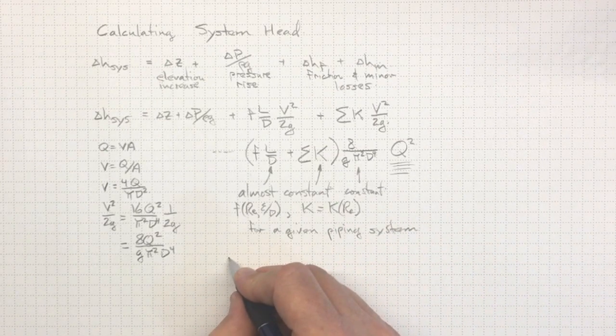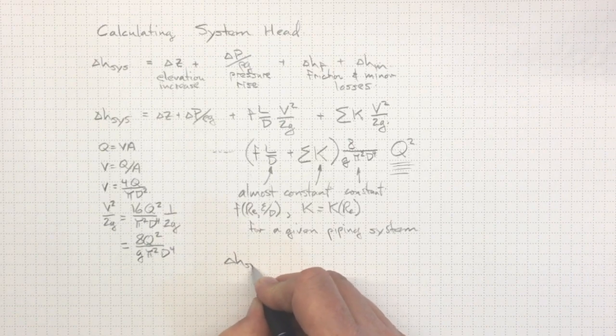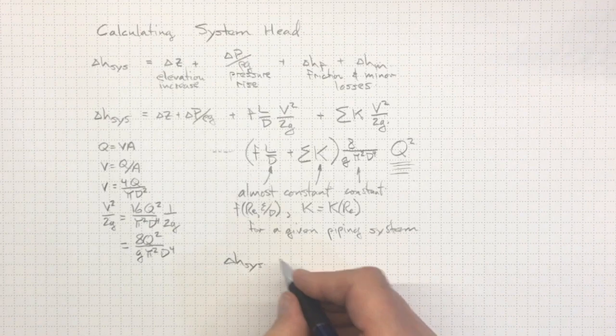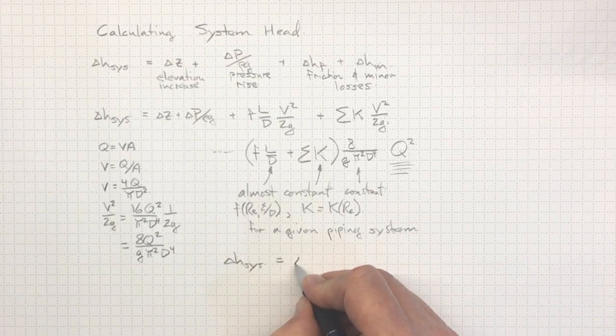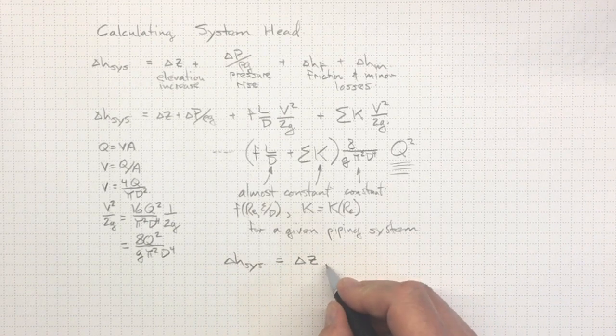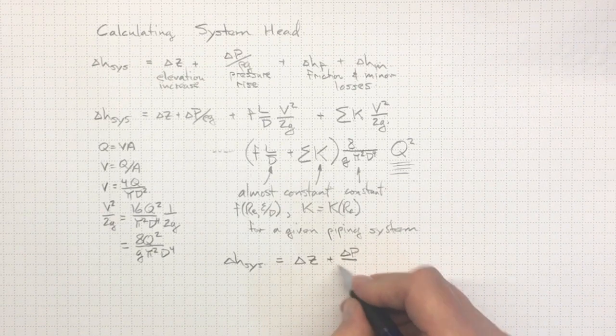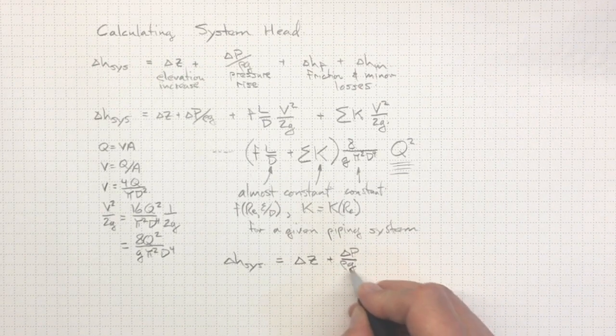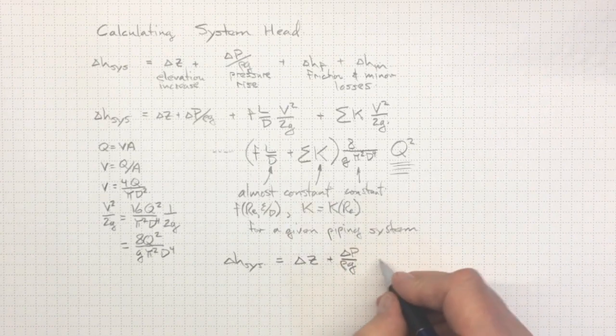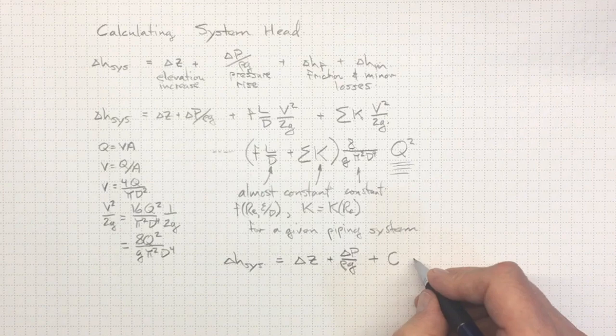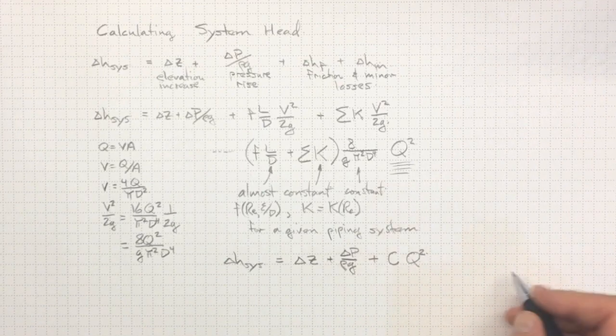So we'll wind up with our system head difference, what we need the pump to deliver in order to supply the system, dependent on the change in elevation, how much we're going up the hill, plus the change in pressure divided by rho g, how much head we need to overcome the pressure difference, plus something that we can treat as just about a constant times q squared.